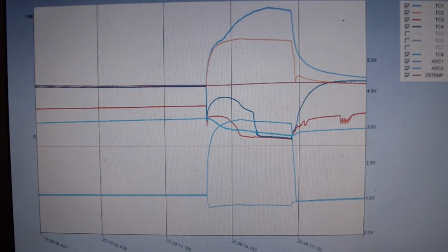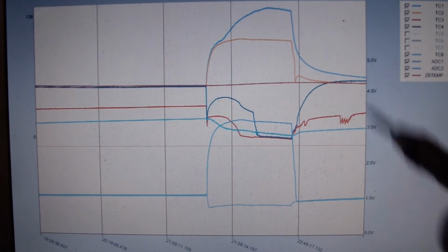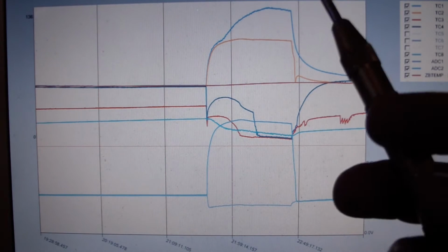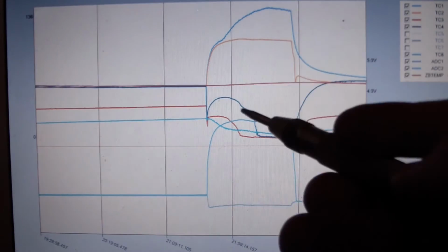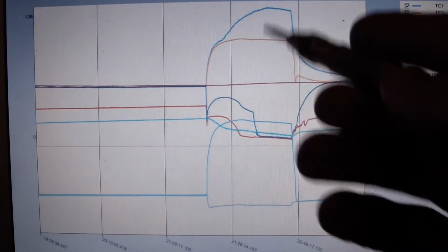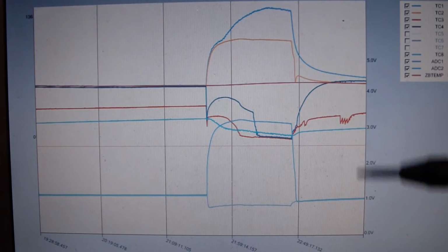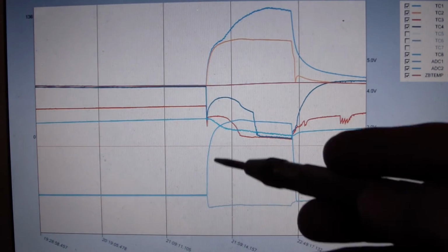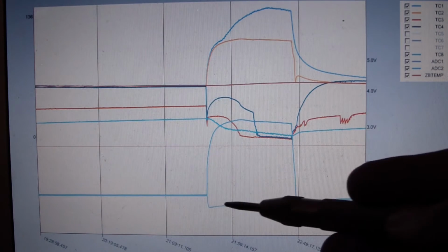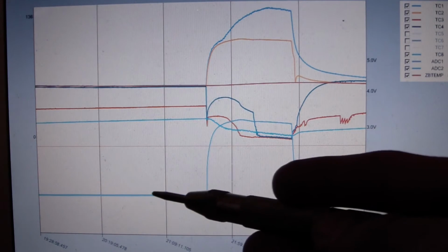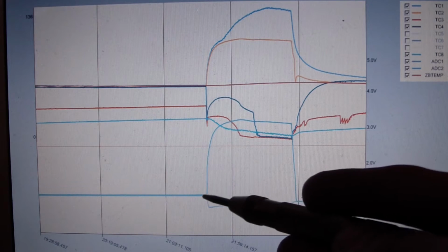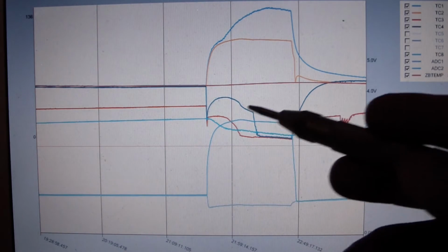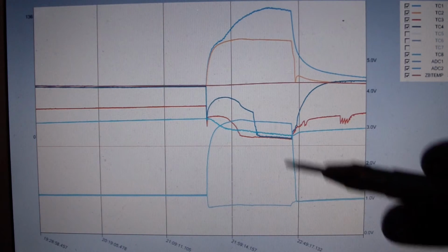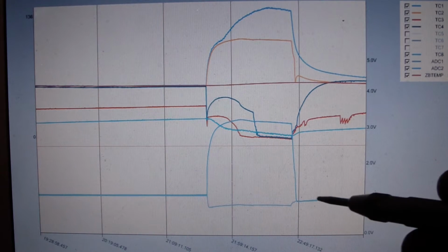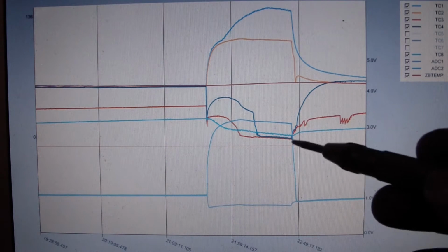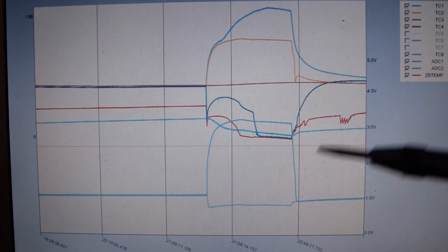So one of the first things I wanted to point out here is that we have some new information here. Before we had just the temperatures, which are all these color lines above. Now we have voltages here too, so that's the pressure transducer. Here's the high side pressure, here's the low side pressure for a run. So you can see they were at equilibrium, and then the low side drops and the high side of course rises during the entire run. Whenever the thing shuts off, we go back into equilibrium over the course of a couple of minutes or something like that till the high side pressure drops.